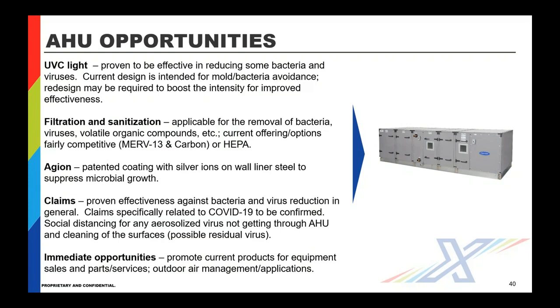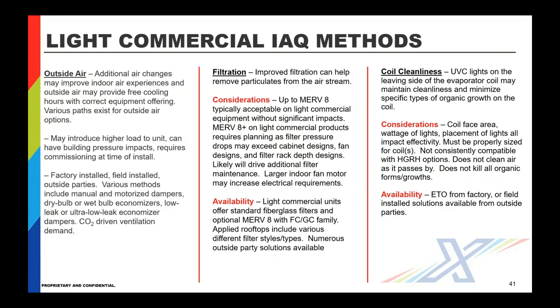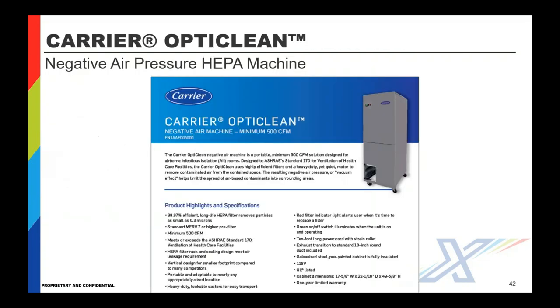Before looking at the negative pressure machine, even our standard air handlers can incorporate UV light and will incorporate HEPA filtration as needed — both standard and custom units. The AGIon antimicrobial silver ion lining can be integrated into standard units as well as rooftop units. Some rooftop units can be retrofitted to higher filtration levels, some can't — we need to check that the fan system can handle the filtration requirement. Most hospitals now start with a MERV-8 by code, and we can go up to HEPA filtration at the air handler level before distribution throughout the building.